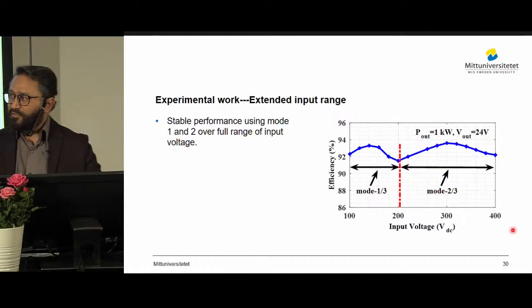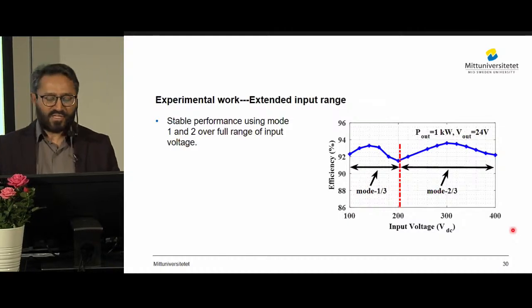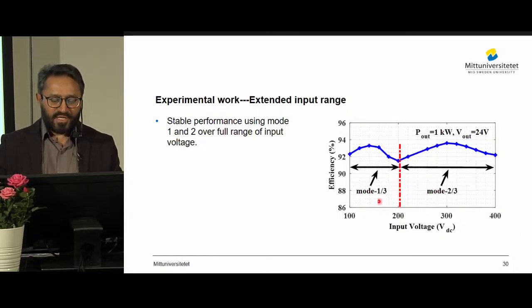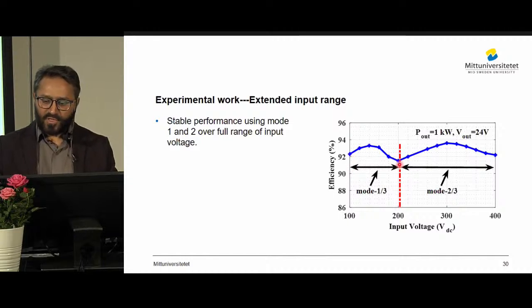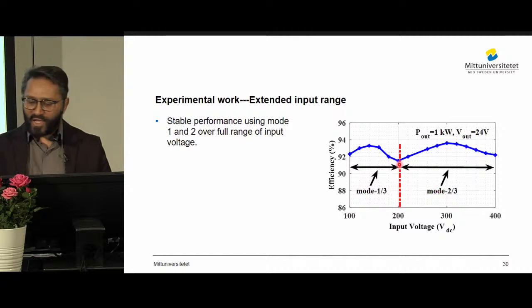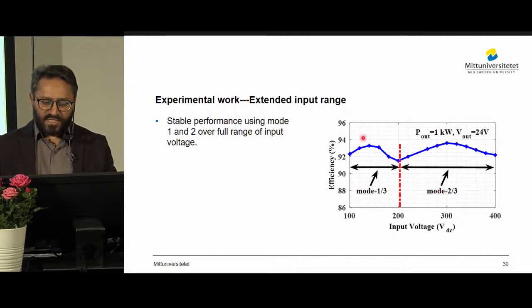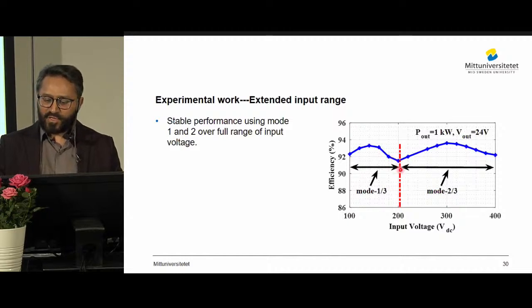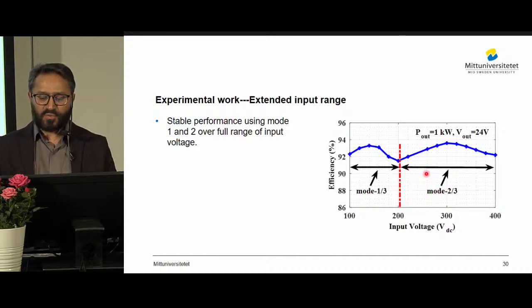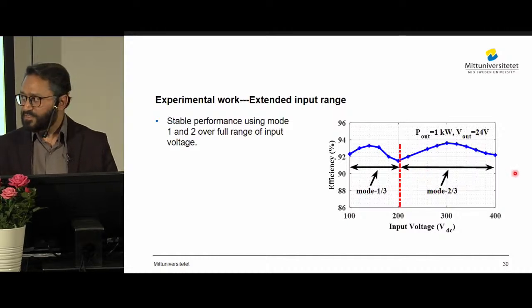The performance of the converter has also been investigated over the full supply range. As seen, it keeps the performance stable. From 100 to 200 volt the converter operates in mode 1, and efficiency decreases due to the increase in input voltage. As the supply voltage crosses 200 volt, the converter switches to mode 2, resets the duty cycle high again, and makes the performance stable.